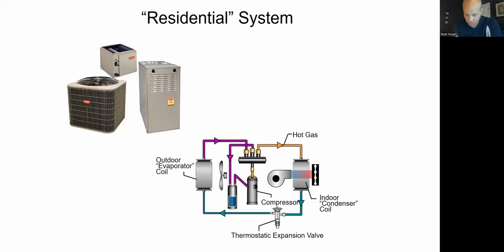All right, so these residential systems that I was mentioning, get my laser pointer. All right, so we have an outdoor coil. That's this guy right here. Indoor coil. He's right there. He's going to sit above our furnace, or it could be built into a residential air handler system. We have a compressor sitting outside. We have an expansion device sitting inside at the coil, and then we have our reversing valve. Once again, the reversing valve is really the only moving part that is different than a standard air conditioning system.